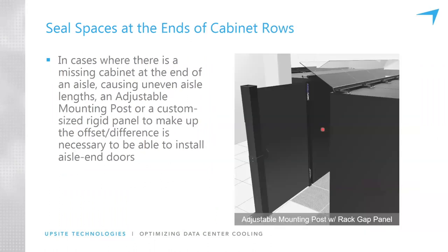Another important consideration is making sure that the aisle ends are even. And this is done in this case with an adjustable mounting post and a rack gap panel to seal up that space. This can also be done with a rigid panel, a number of different ways to seal this space and align the ends of the aisle so that doors can be added to the ends of the aisle.